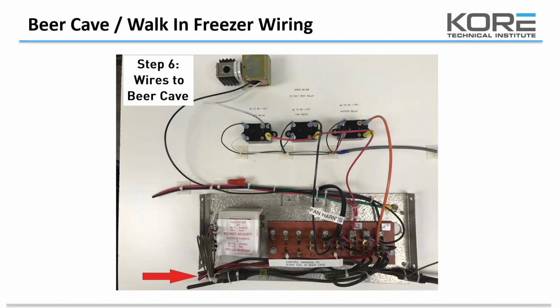One difference in this that I did not put in this picture is we do have a double pole single throw relay that we are using. One heater circuit for the master coil will go through one side of that particular relay, and then the slave will be on the other, and that's due to the amount of amperage that has been going through these relays. So that would be the only difference from this.